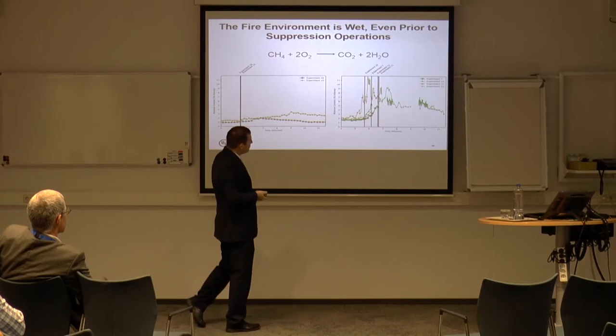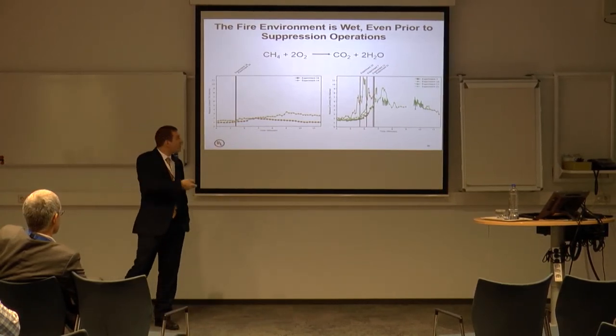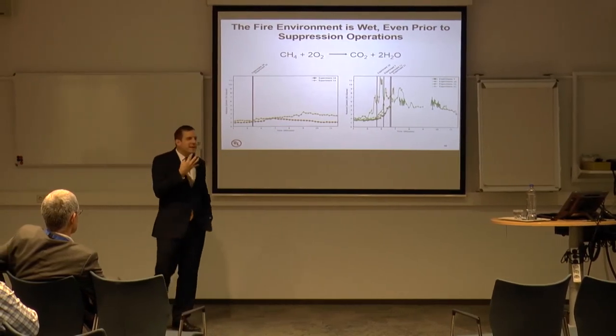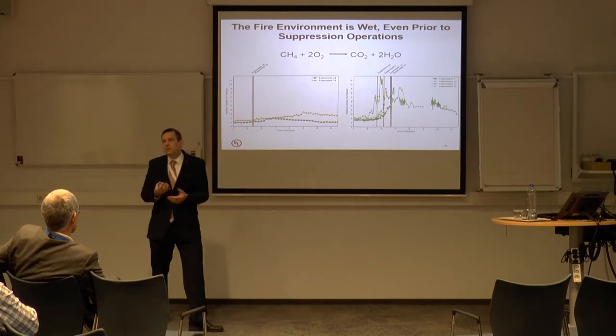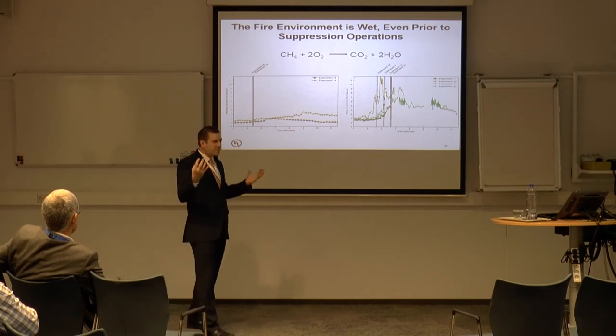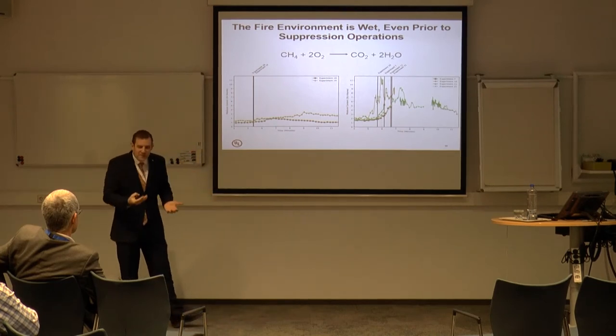That up there at the 5 foot level was already so wet because of the smoke that had moisture as one of the products of combustion in it, that you physically couldn't get any more moisture in it. So even though you were spraying 325 liters a minute of water into that structure, it can't become a gas and be trapped in the gas because there's just not enough room. It drops out as condensate.